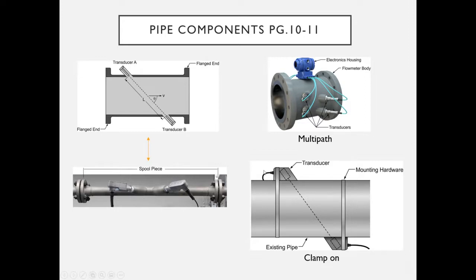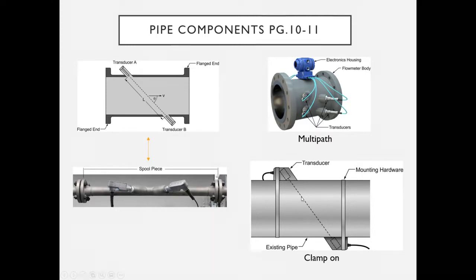The clamp-on ultrasonic meter is another installation style. These come in portable cases and can be clamped onto any acoustically transmittable pipe to verify flow of other meters in the field. They are a very handy tool for diagnostics, identifying pluggages, and verifying flows without interrupting the process.